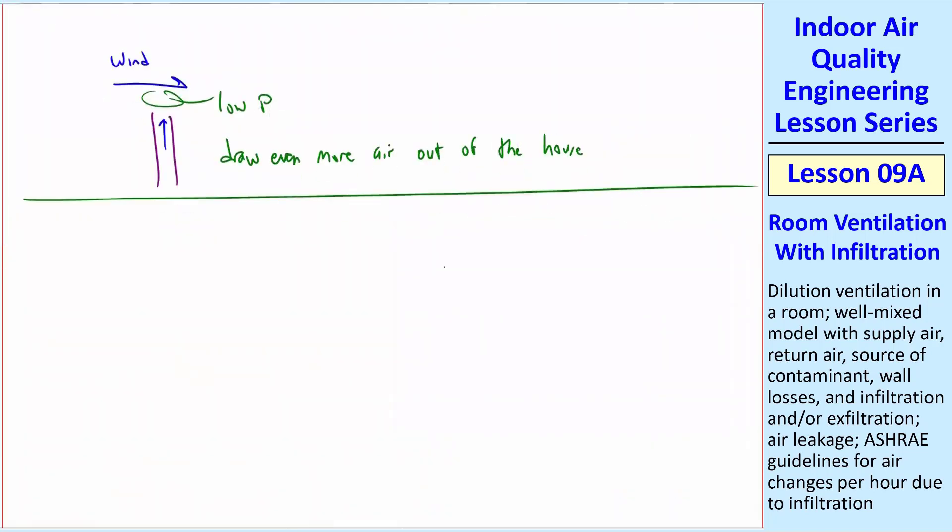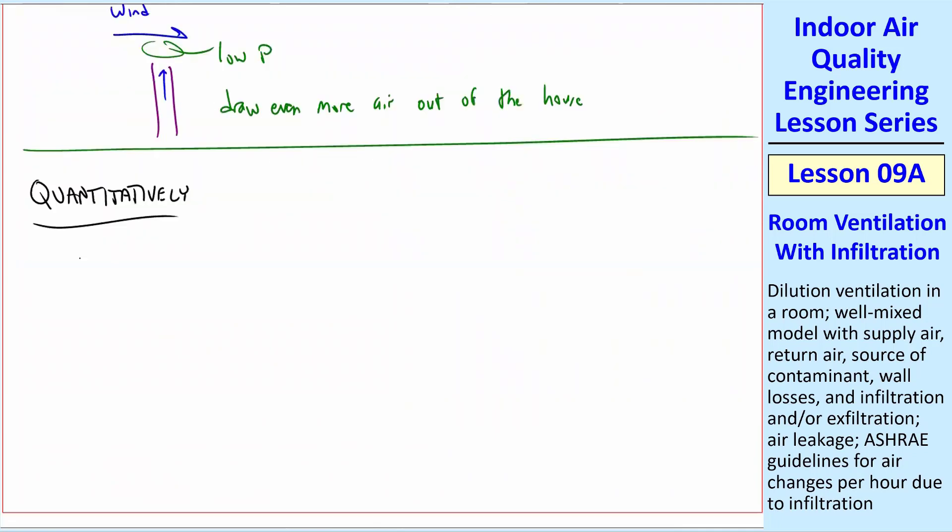What I want to do now is look more quantitatively. A couple of comments before we get to equations. Infiltration and exfiltration are typically in units of air changes per hour. Recall, for a room, we had N equal Q over V, the flow rate divided by the volume. So this is the number of room air changes per hour.